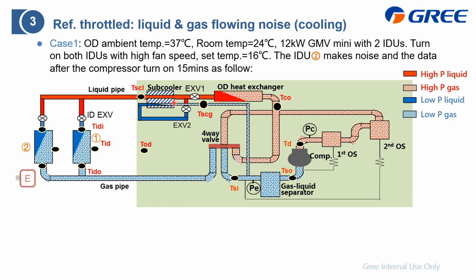And then this part, a partial refrigerant will become from liquid to gas, then flow back to the gas liquid separator. And as the main load, it will become cooler, and then it can flow further to the furthest one. In this case, it is the number 2 indoor unit. It is the furthest one, and then it makes an exchange inside, and before that it will get expanded at this indoor unit EXV, and then become low temperature and absorb heat, which is doing cooling, then become gas and flow back to the outdoor unit, then to the gas liquid separator. And the problem here is this indoor unit 2, which is also the furthest one. So here is the refrigeration cycle, and we will analyze the data.